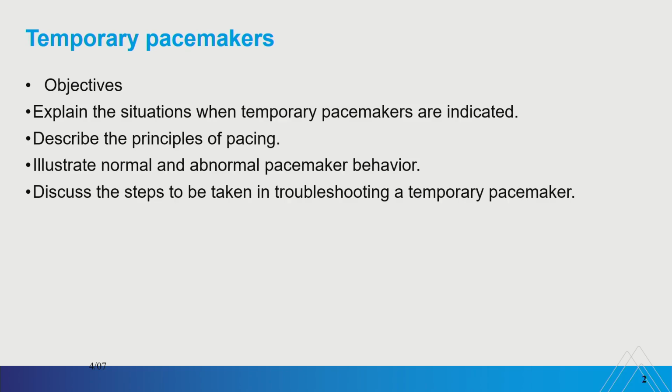So I'm going to make an assumption that a lot of you have used external pacemakers in your practice. Regardless of the brand that you use, the settings will all be the same. Milliamps will be milliamps, millivolts will be millivolts. It's all the same, and they usually have very close to the same defaults on these pacemakers.